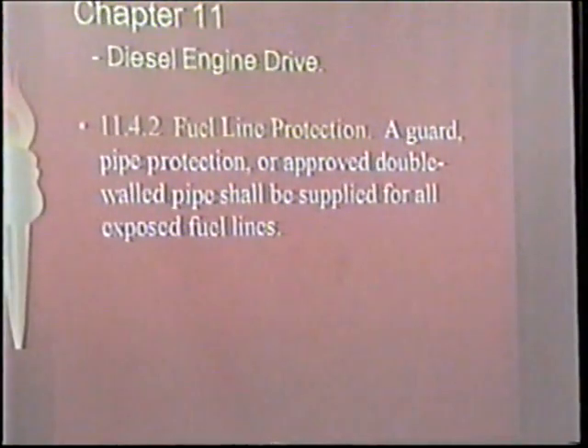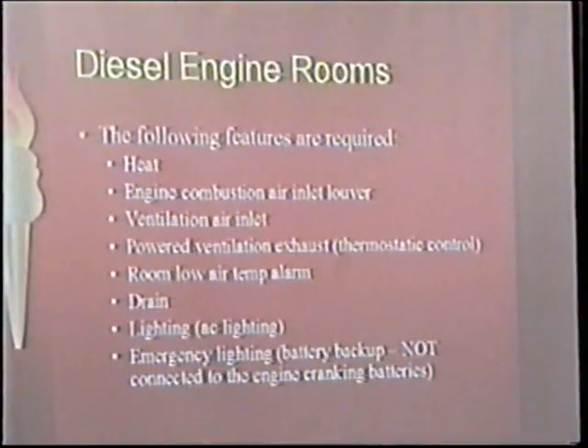Dave, where does that room low air temp alarm go? Typically, what is that connected to? Well, typically what we try to do is provide it as part of the fire pump controller, and then it comes out as one of the common alarm points. So that would be one of those supervisory points? One of those points that we're going to come down to here as far as the required alarm hookups. It would be nice if people would break it out as a second alarm, but unless they order it that way on the controller, it's not going to be capable of that. We can always field modify it, but that's not a standard.